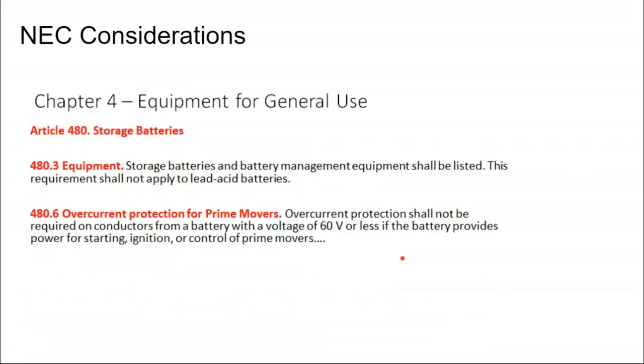That's kind of interesting. What that says is, if I'm automatically transferring a 25 amp dedicated output to a 200 amp service panel when the power goes out, that could be a National Electric Code violation.